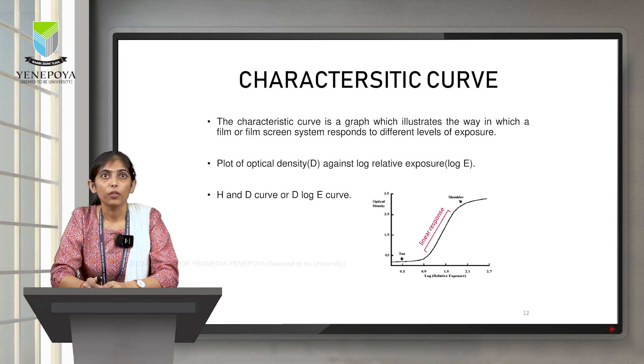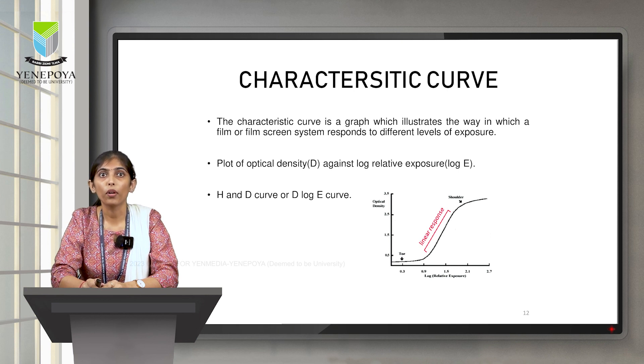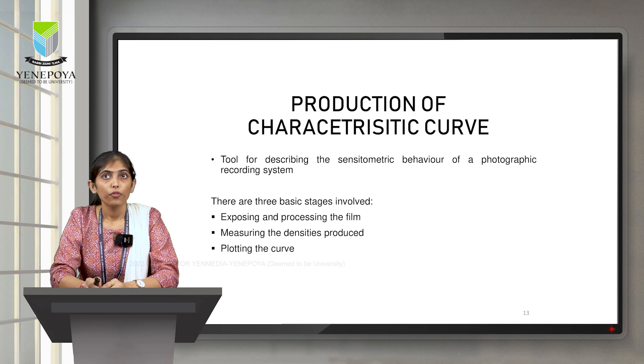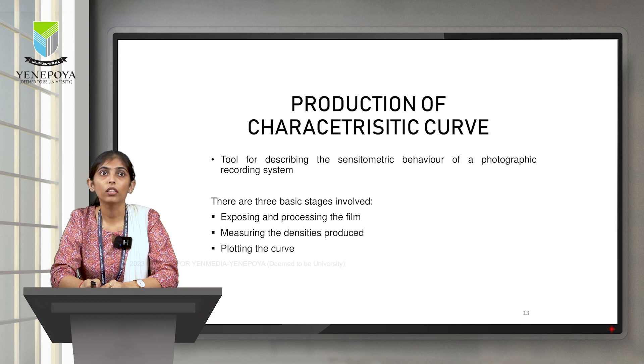Coming to the characteristic curve — it is a graph which illustrates the way in which a film or a film-screen system responds to different levels of exposure. This graph is plotted between optical density on the y-axis versus log relative exposure on the x-axis. This curve is also known as the H&D curve or D log E curve. The production of the characteristic curve involves three basic steps: exposing and processing the film, measuring the densities produced, and plotting the curve.